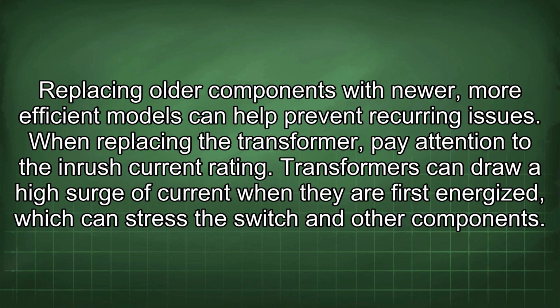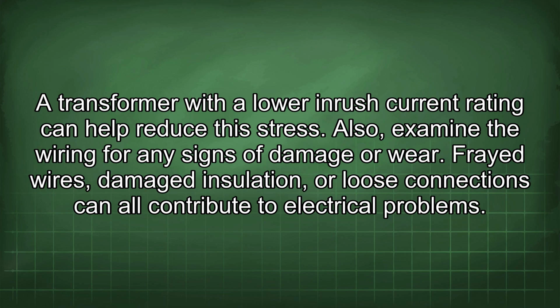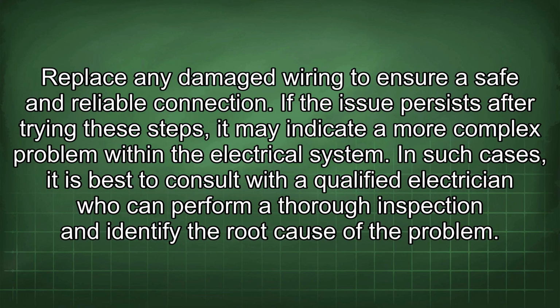When replacing the transformer, pay attention to the inrush current rating. Transformers can draw a high surge of current when they are first energized, which can stress the switch and other components. A transformer with a lower inrush current rating can help reduce this stress. Also, examine the wiring for any signs of damage or wear. Frayed wires, damaged insulation, or loose connections can all contribute to electrical problems. Replace any damaged wiring to ensure a safe and reliable connection.